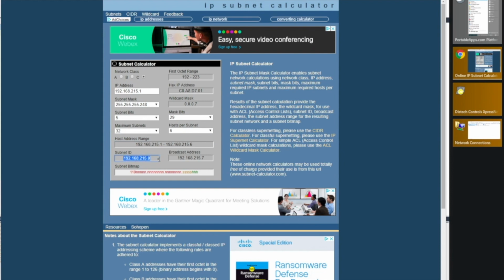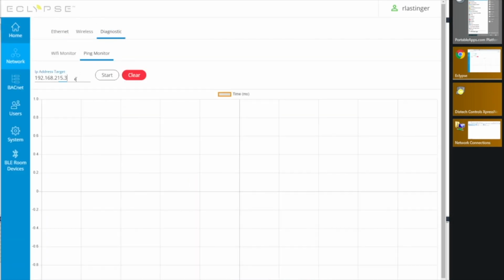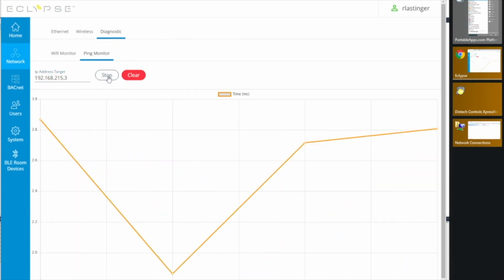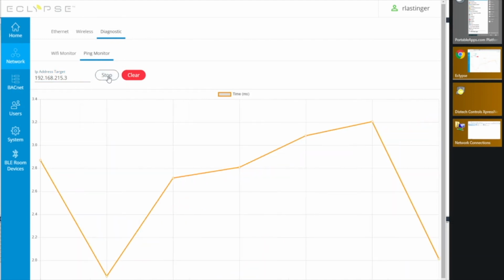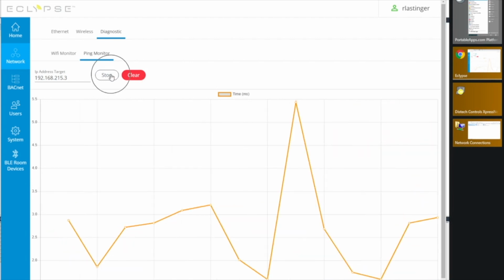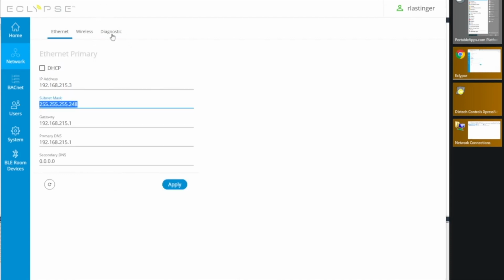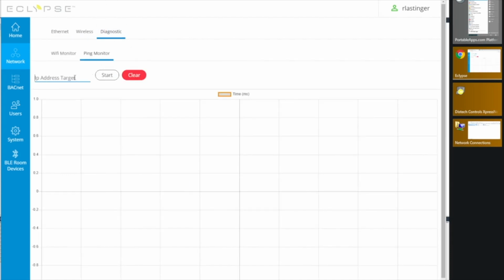So this is why we really recommend using a calculator like this, because it really simplifies the process and removes error for you. Because once you just put your IP address in, likely for your computer, and then fill in the number of hosts you want, it'll give you the subnet. And you see here, since we're on the same subnet, 248, and the addresses that are assigned to the controllers are within those 6 addresses in my host range, we can talk. So we'll ping both ways.